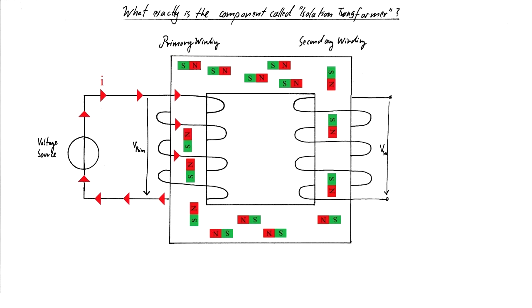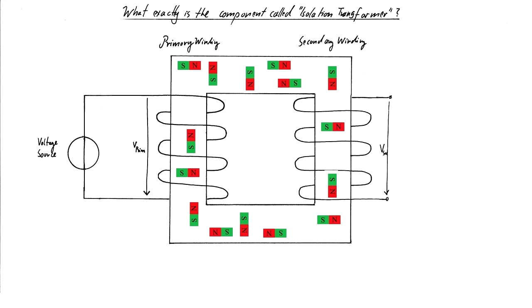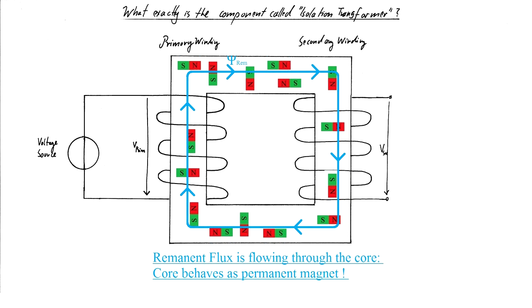This will go on as long as a sufficiently strong AC is flowing through at least one of the windings. When the current is turned off, the elementary magnets will reorient themselves chaotically, but chances are a certain portion stays aligned with the magnetic flux from the last half period when current was still flowing. Thus, a remanent magnetic flux keeps flowing through the core even though no current is flowing anymore. The core behaves like a permanent magnet, and this remaining field is called remanence.